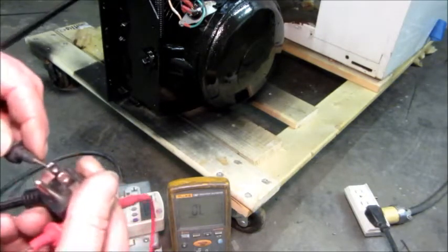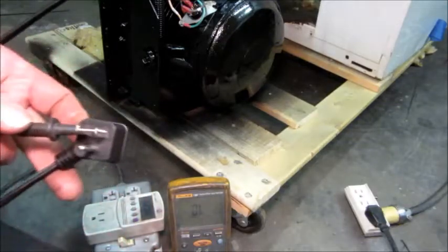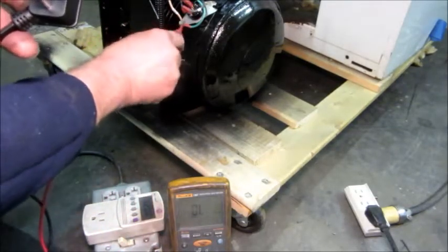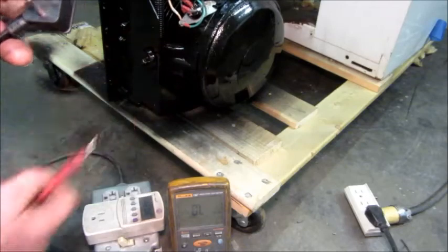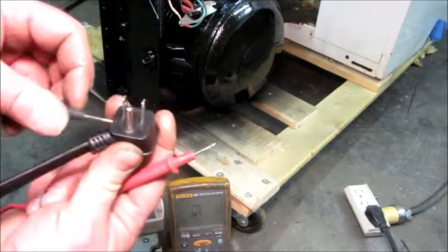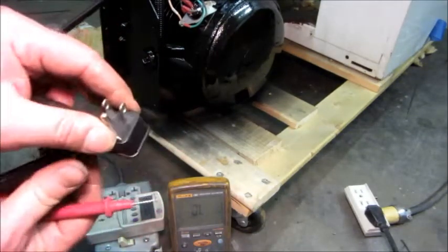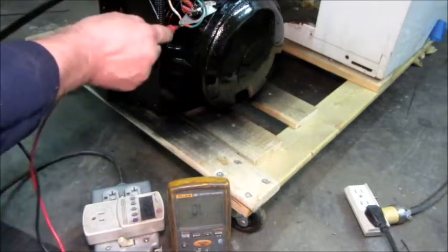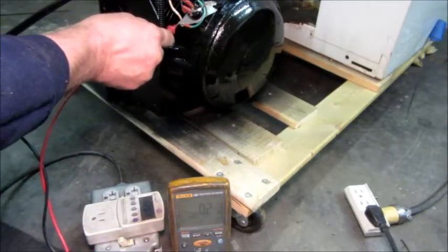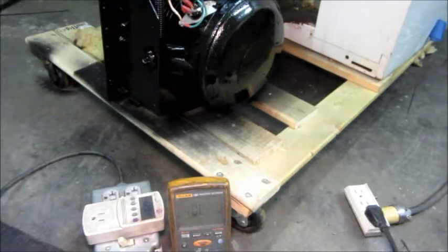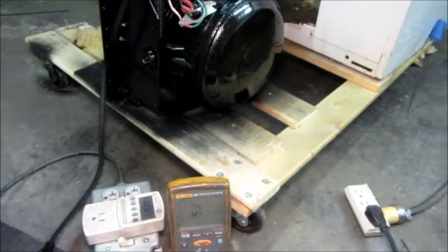Next thing I'm going to do is check from both of the power pins to ground. So I've got no continuity, there's no ground fault. Now I'm going to go from the grounding pin on here and check to ground. And it shows a solid connection. So that tells me that there's no shorts in the system.